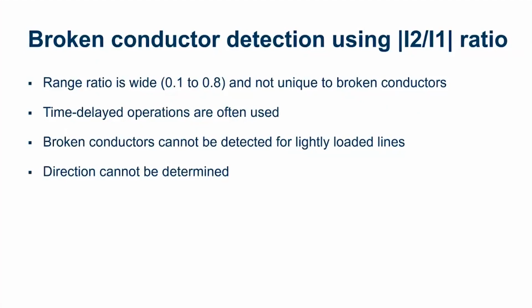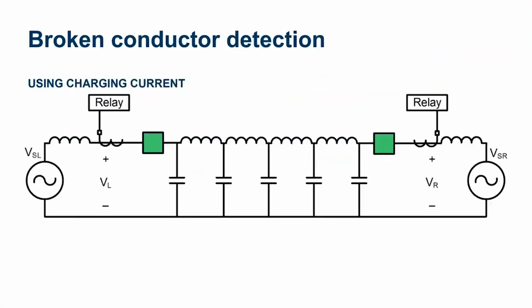So what we have coming up, as Hardesh mentioned, is broken conductor detection that's going to be using charging current only. This is going to be available in the 411L in the coming months in the next firmware release. This is going to be added. Currently, none of this is in our relays right now. But we're going to use this new algorithm in the 400 series relays, and it is going to be run every 8th cycle.